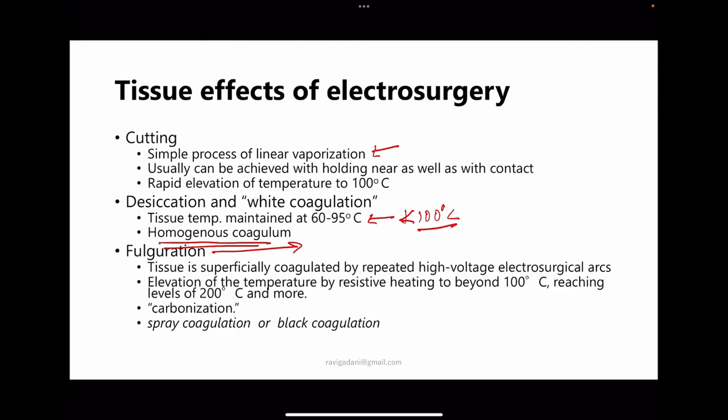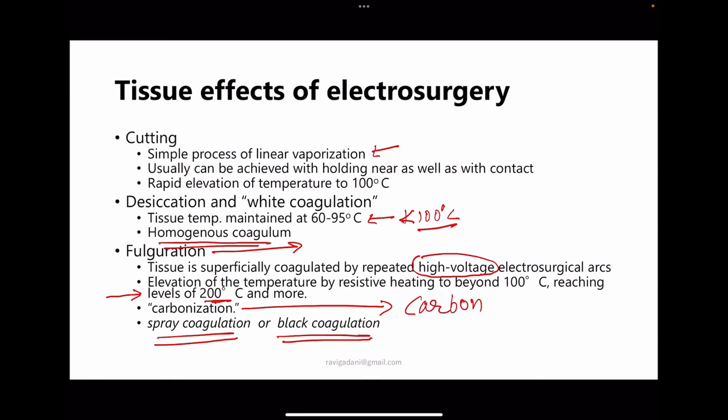Desiccation or white coagulation occurs at temperatures below 100°C: the cell wall is damaged, water leaks out, remaining cell contents form a coagulum as protein denatures, with hydrogen bonds breaking and reforming as the cell alternately heats and cools — creating a homogeneous coagulum. Fulguration uses very high-voltage electrosurgical arc, elevating temperature to 200°C or more; the carbon within the cell is released, producing black eschar — also called black coagulation, spray coagulation, or carbonization.